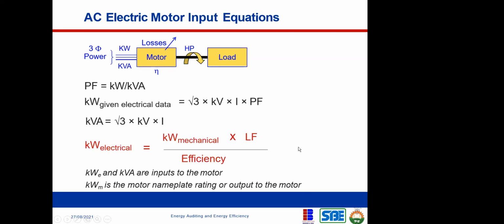Now let us look at the formula that helps us connect kilowatt electrical to kilowatt mechanical. This is the formula, written in red. Kilowatt mechanical is the output, the shaft output. When you look at the nameplate ratings of motors, you're going to see their capacity. What you're seeing there is kilowatt mechanical. When you look at the nameplate, this is important.